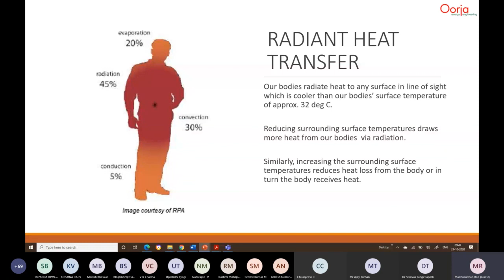The moment we started reducing building thicknesses, the heat had less resistance, and therefore the inner wall surfaces started rising to an extent that now sometimes the external wall isn't even there — there's just structural glazing of 4 mm. So the inner surface temperatures that we are exposed to today sometimes exceed 40 degrees centigrade, and that is why we require more cooling.